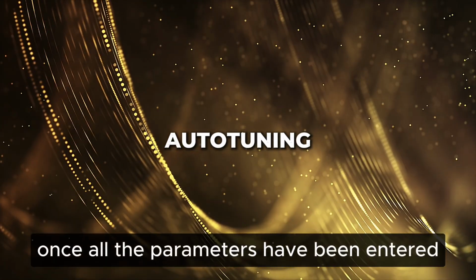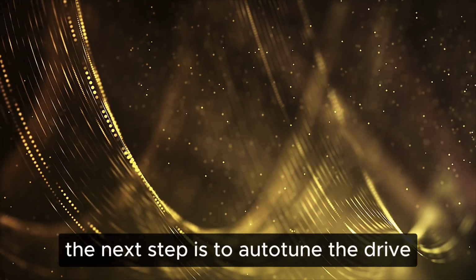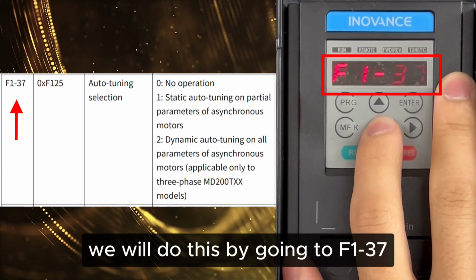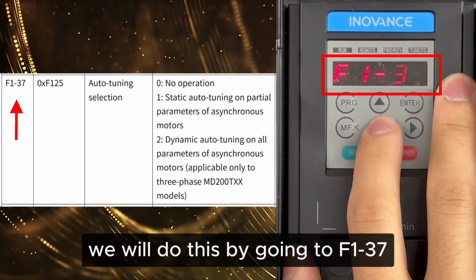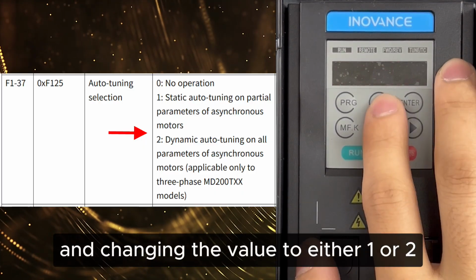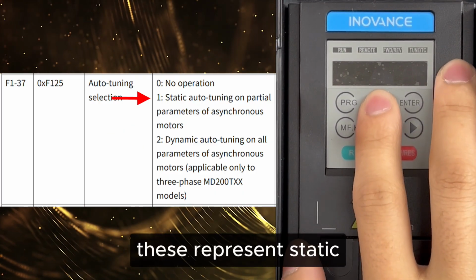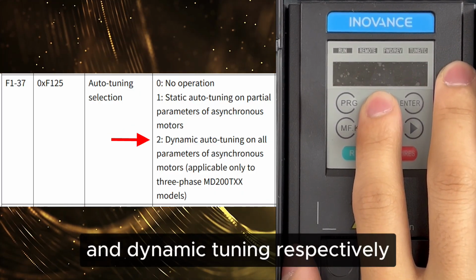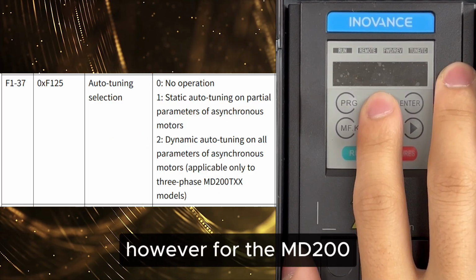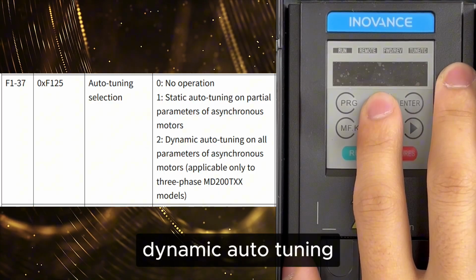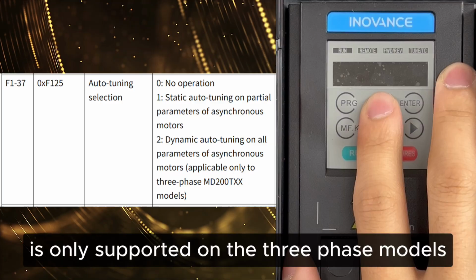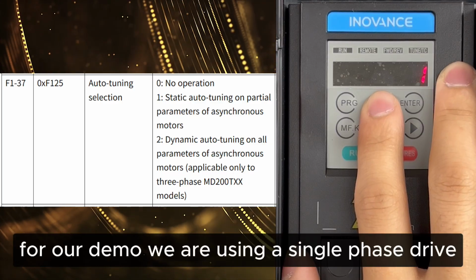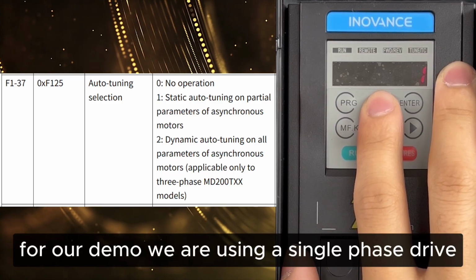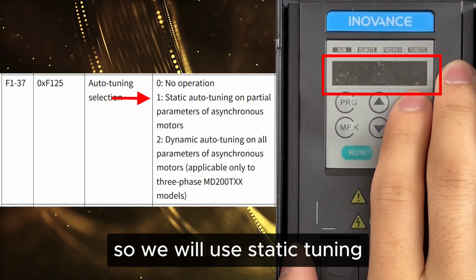to save. Once all the parameters have been entered, the next step is to auto-tune the drive. We will do this by going to F1-37 and changing the value to either 1 or 2. These represent static and dynamic tuning respectively. However, for the MD200, dynamic auto-tuning is only supported on the 3-phase models. For our demo, we are using a single-phase drive, so we will use static tuning.